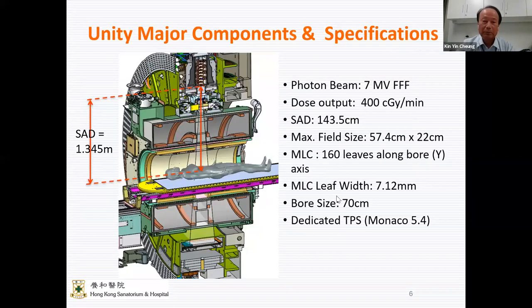Now, let's go to a bit of the machine itself. This shows the basic structure of the machine. On top is the waveguide. It's a 7 MV photon beam, FFF radiation beam. It goes through the collimators and the beam monitors onto the patient. The isocenter is 1.345 meters away from the source. And after the patient, it goes to an MV imager. It's not for patient setup, this imager. It's for QA and beam alignment purpose. And then there's a beam stopper to reduce the transmission and also reduce the amount of shielding required.